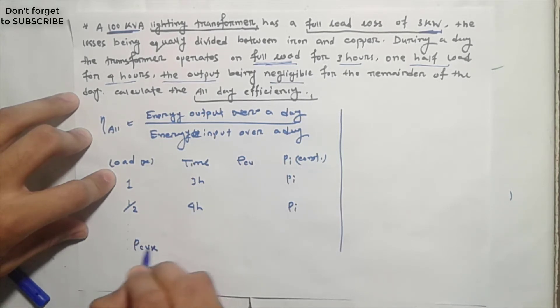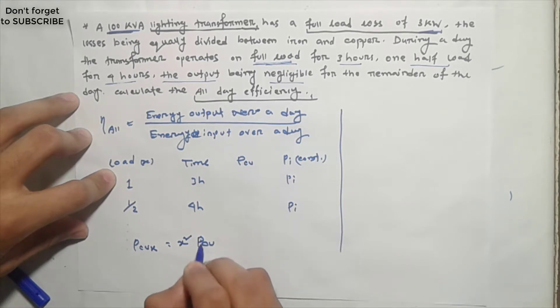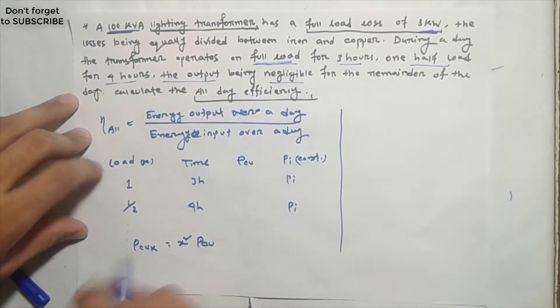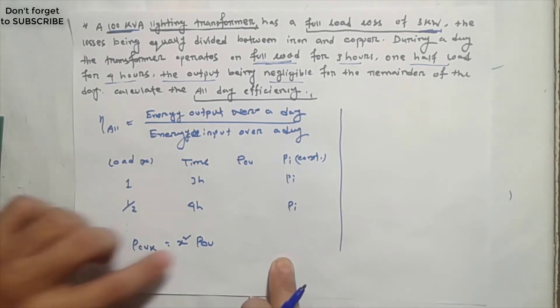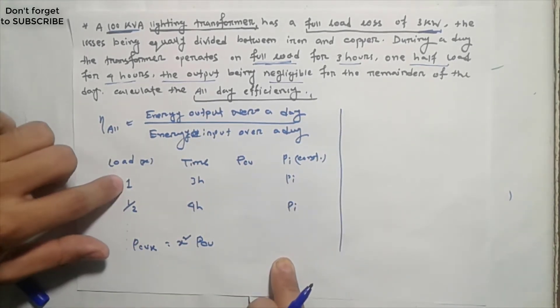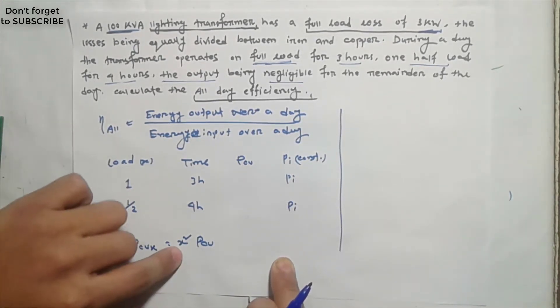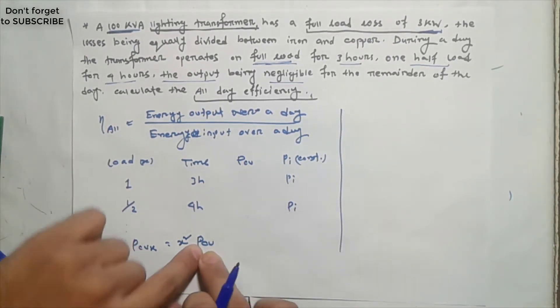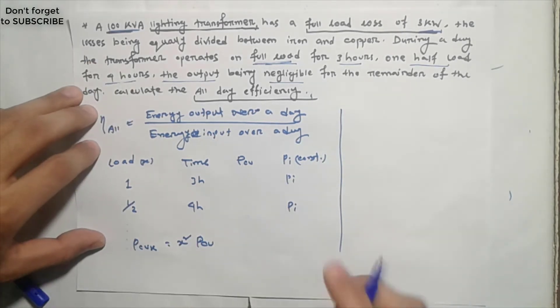The copper loss is given by x-squared times PCU, where PCU is full load copper loss. So x-squared is the fraction of load squared. For full load, x is 1 squared; for half load, x is one-half squared. PCU is the full load copper loss.